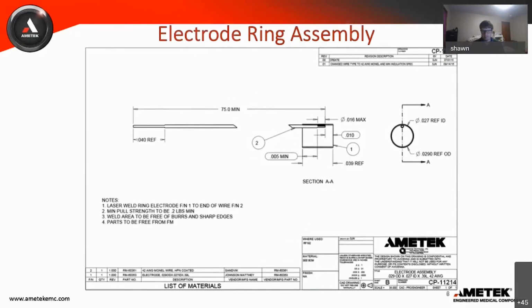Tolerance stack-up for assembly of the ECG sensing electrodes is causing parts to go out of specification. First, let's review the specifications that would influence this. We will review the electrode ring assembly, laser drilled tube, and spline tube assembly specifications.